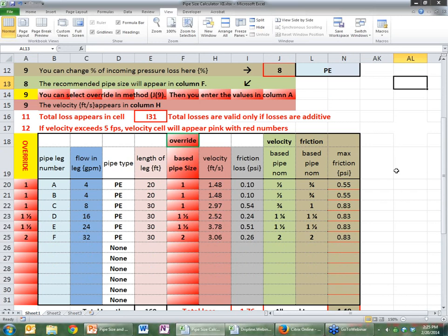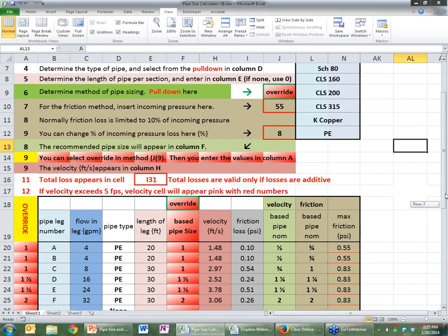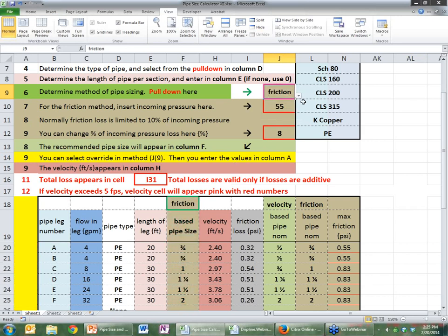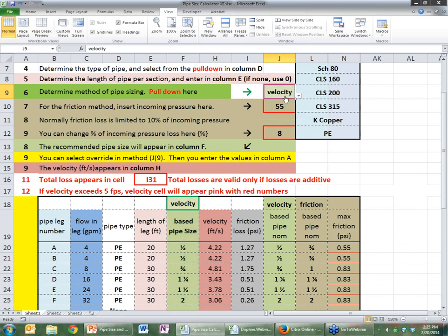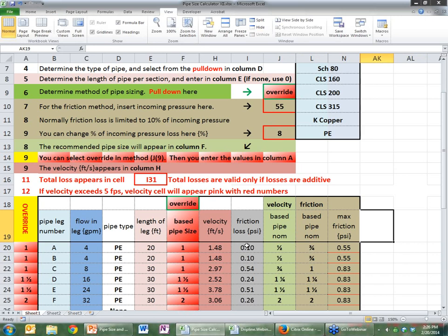Next question. In the velocity or friction mode, can you change the base to pipe size? Yes. Only in override. And what it does is when you change, I see what your question is. No. If you're in friction mode, it sets the pipe for you. If you're in velocity mode, it sets the pipe for you. If you go in override, you can set it. But it will tell you what it would have picked if you had been velocity based or friction based over here. You follow that? If it were velocity based, it would have been half inch. If it had been friction based, it would have been three quarters. But you said one. So this is what you got.